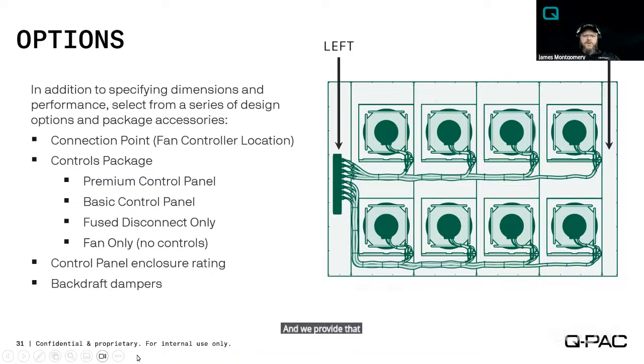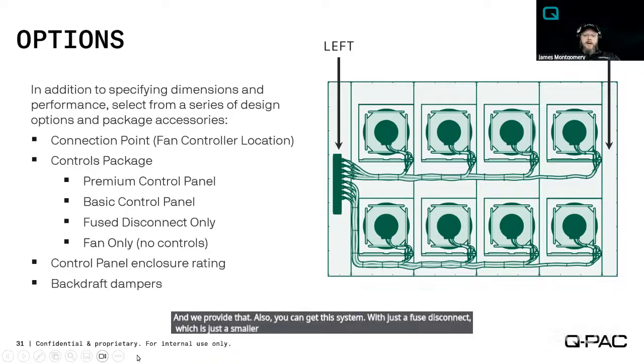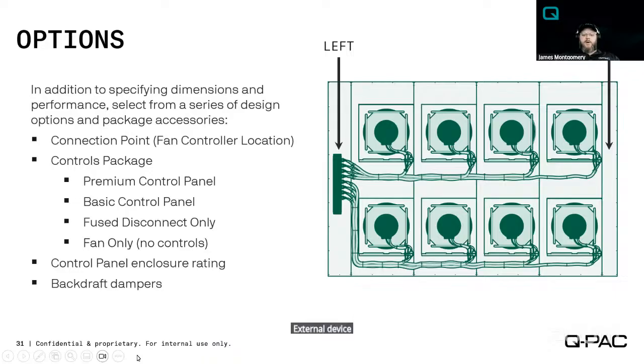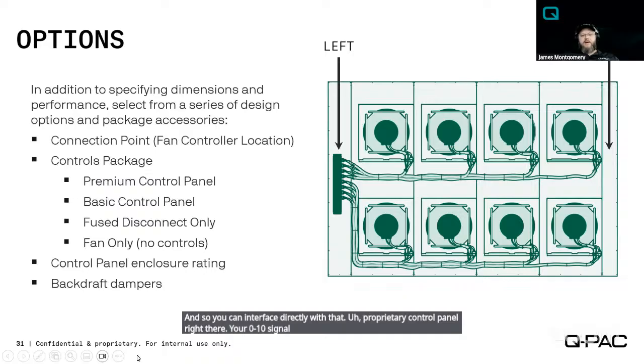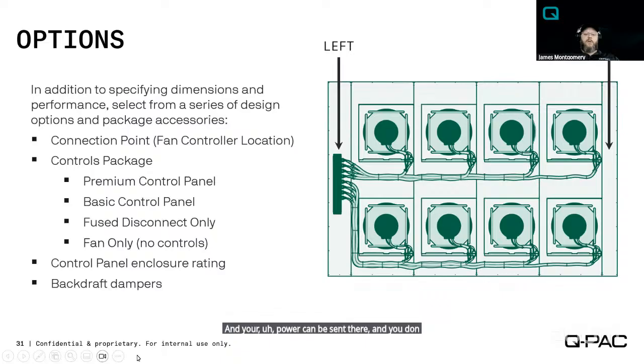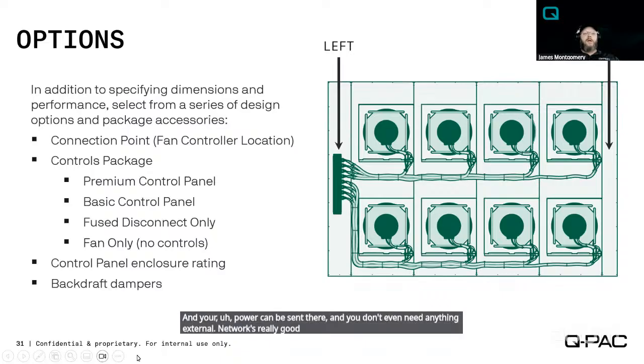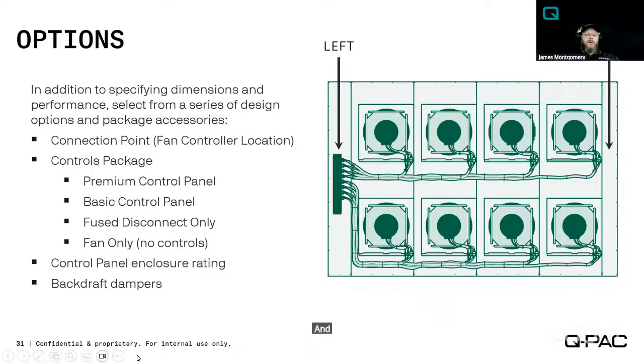Also, you can get this system with just a fuse disconnect, which is just a smaller external device that you would put in between where the power comes in. And then this can be ordered as fan only, no controls at all. And so you can interface directly with that proprietary control panel right there. Your 0 to 10 signal can be sent there, and your power can be sent there, and you don't even need anything external. And that works really good for rooftop units and units that have existing controls.